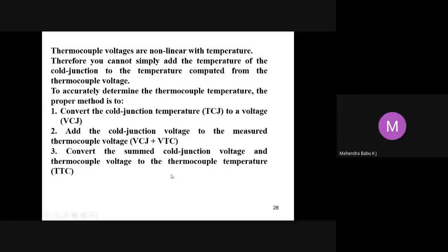Thermocouple voltages are non-linear with temperature, so we cannot simply add the temperature of the cold junction to the temperature computed from the thermocouple voltage. In order to accurately determine the thermocouple temperature, the proper method is to convert the cold junction temperature to a voltage and add this cold junction voltage to the measured thermocouple voltage. Then convert the summed cold junction voltage and thermocouple voltage to a thermocouple temperature.